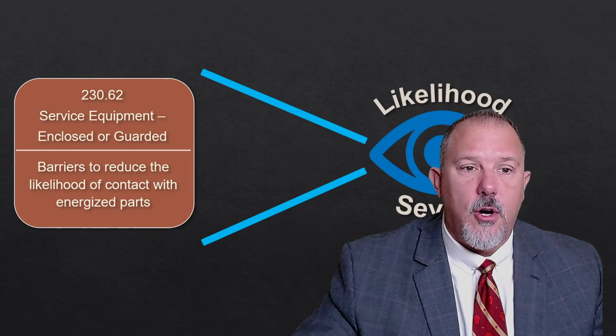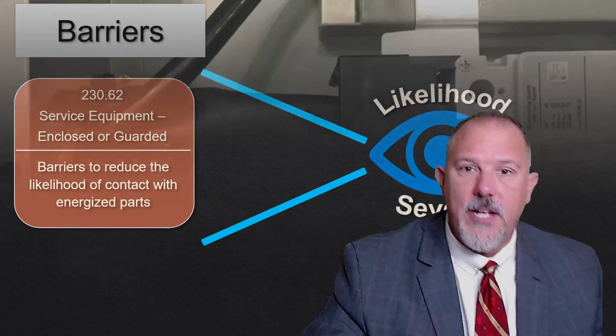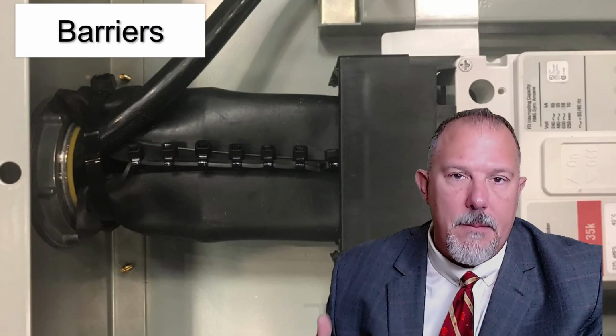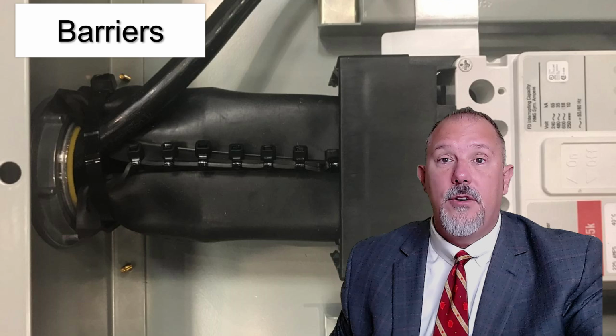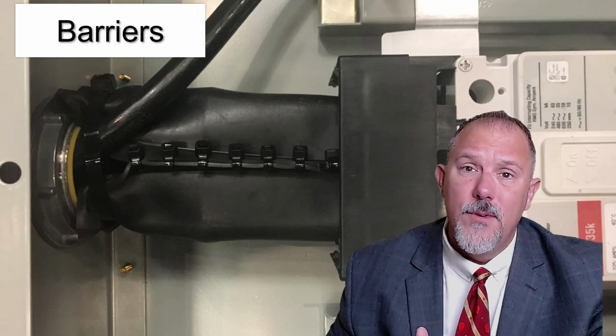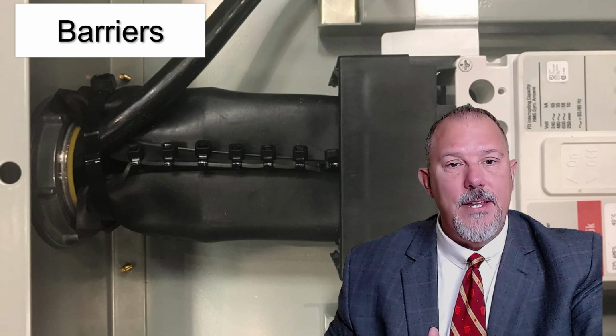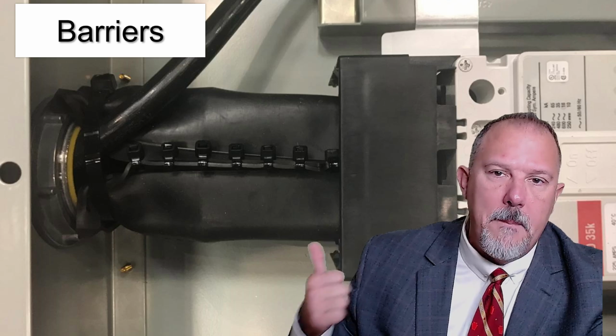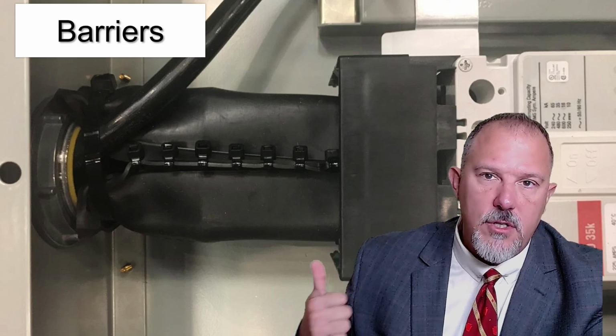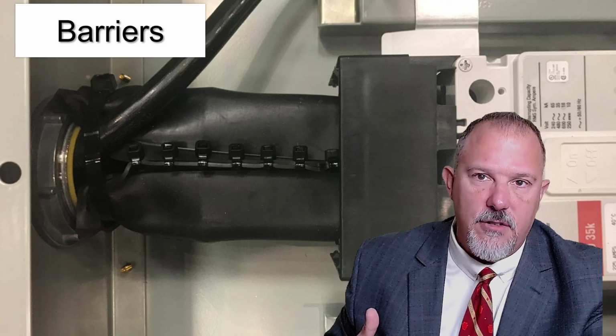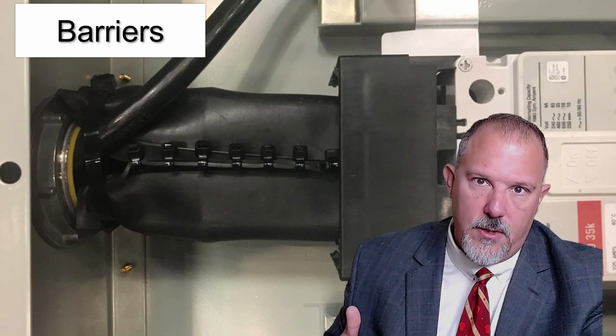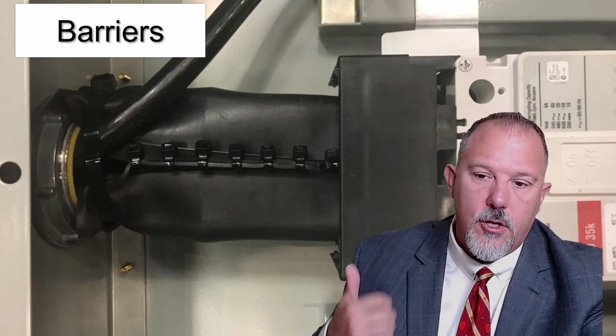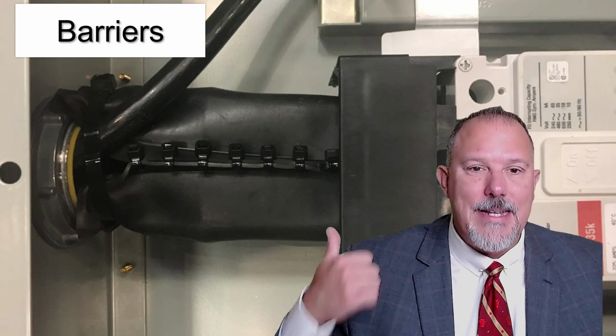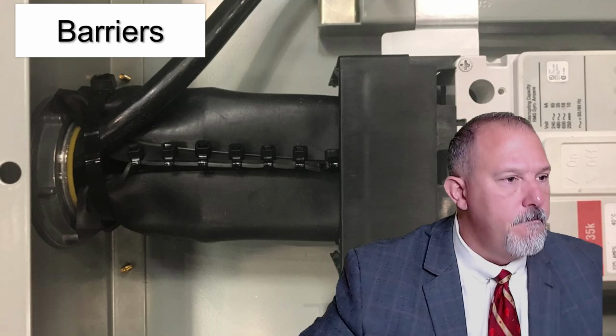230.62, enclosed or guarded. These are your barrier requirements. What am I doing when I add a barrier like this on the primary lugs? I'm reducing likelihood. Am I reducing the energy? No. I'm reducing the likelihood of anybody touching these primary conductors, the exposed energized parts, and causing an arc flash event or getting electrocuted. You're not going to cause an event if you can't get to those lugs.